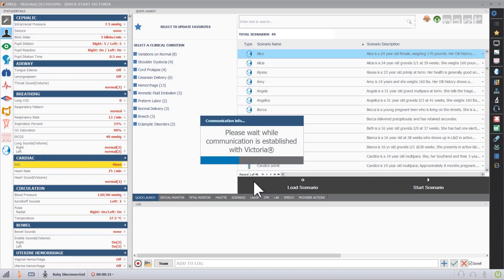The simulator must be turned on prior to calibrating, priming, draining, programming syringes, or injecting fluids into the arm.